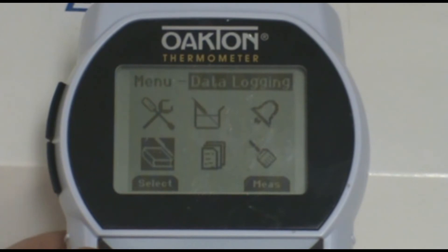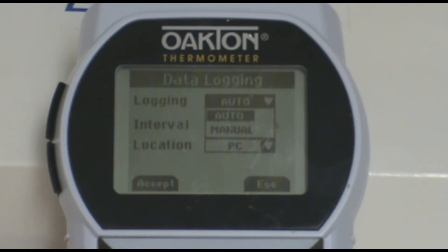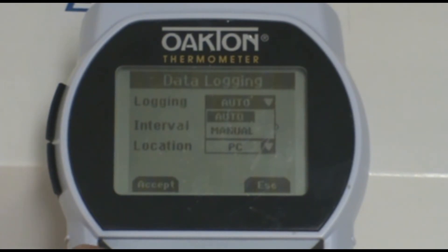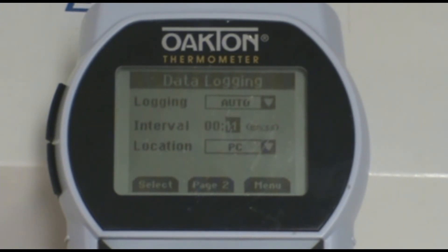Press the Select or F1 button to enter the data logging setup. You can then adjust your parameters based on what will work best for your application. To change each parameter, make sure the field is highlighted and then press the Select button. You can then use the arrows to scroll between the different options. For location, make sure it is set to Meter, and for logging, set it to Auto so that it will automatically take a reading after the time interval you have set passes.